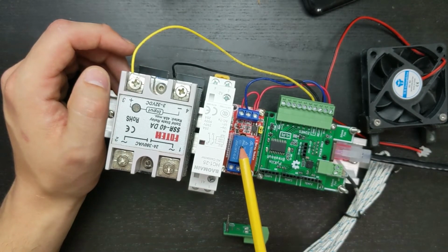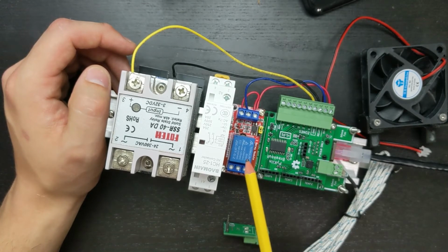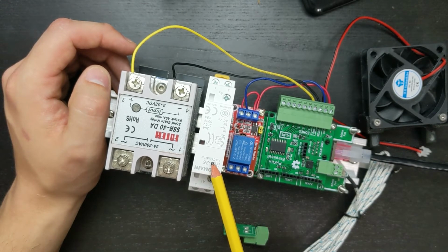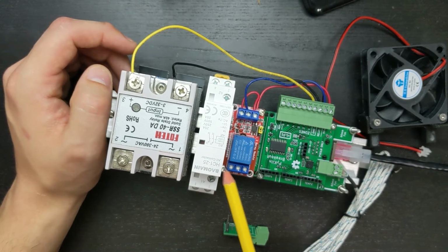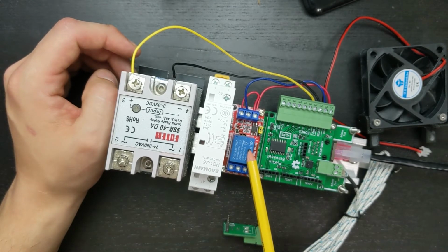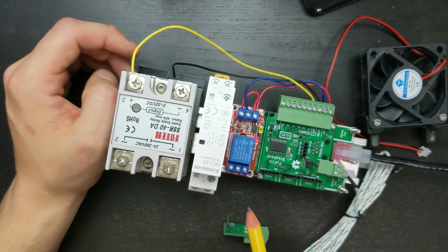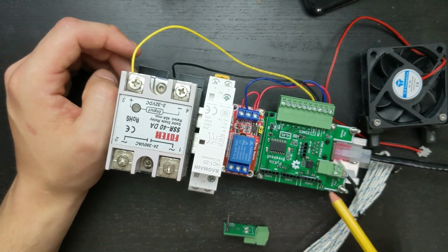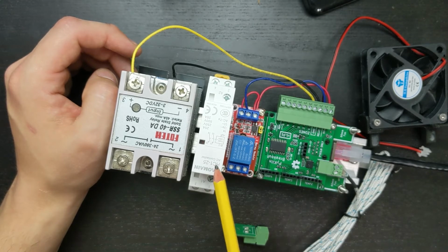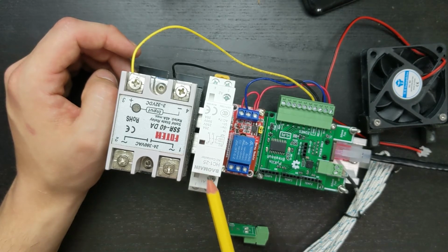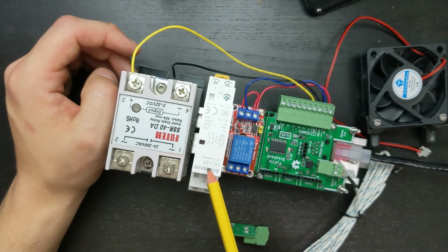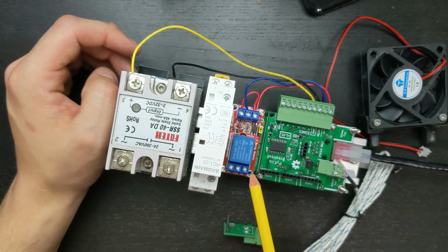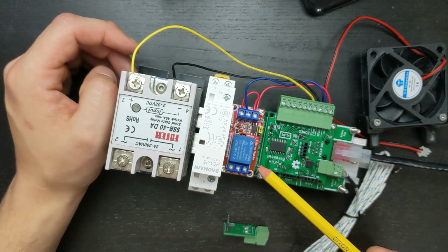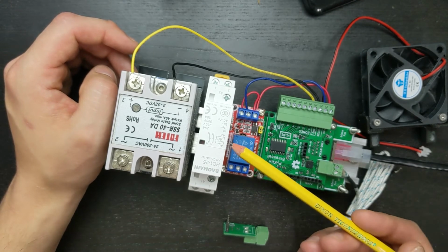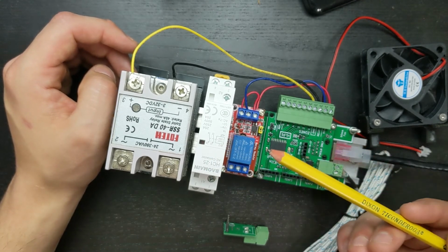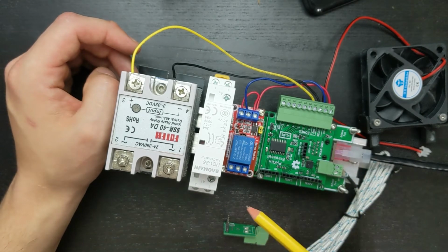So the contactor right here. The relay supplies power to the coil in the contactor, and that way you don't have to have another power supply. They do make other contactors that use like 24 volts for the coil, but it's just a lot easier. You already have 120 volts AC in here, so you might as well just use it. It just makes it a lot simpler.